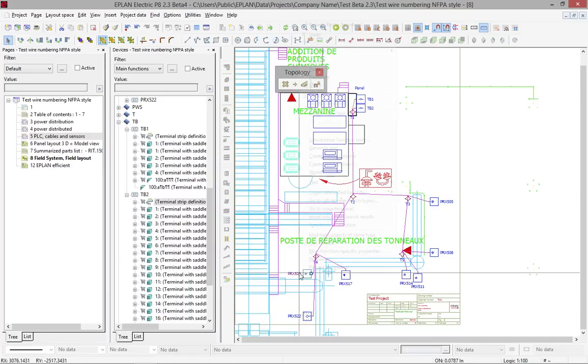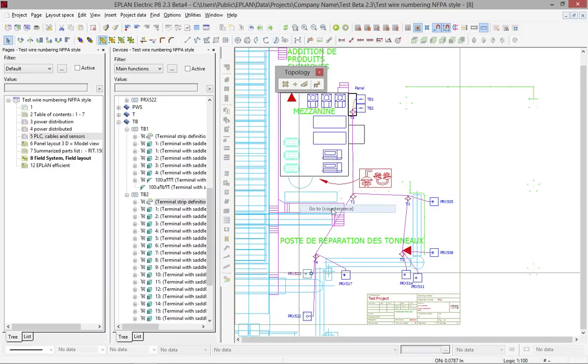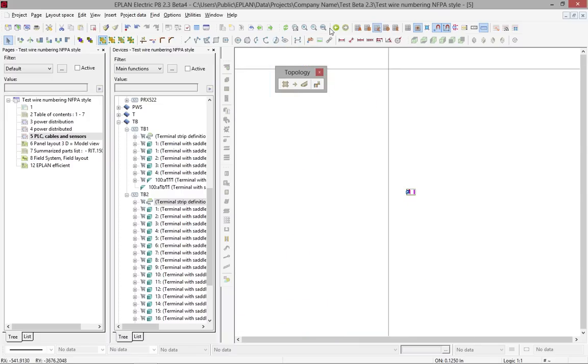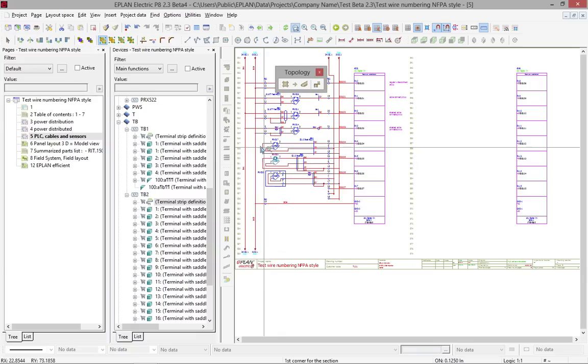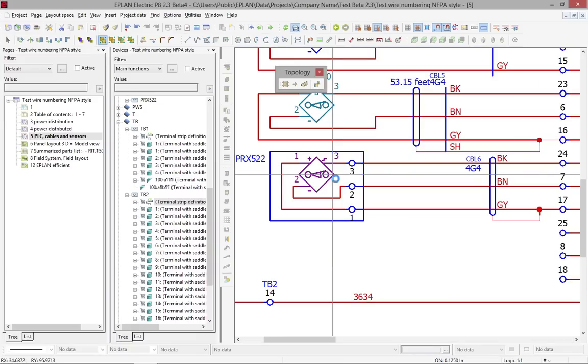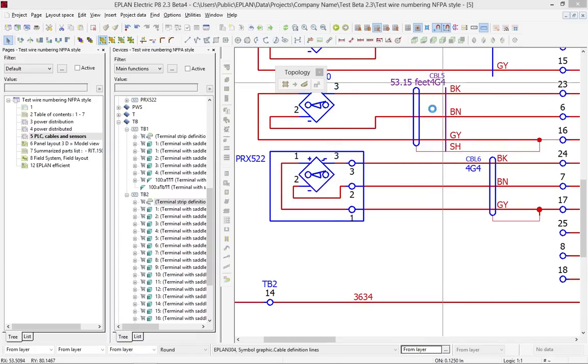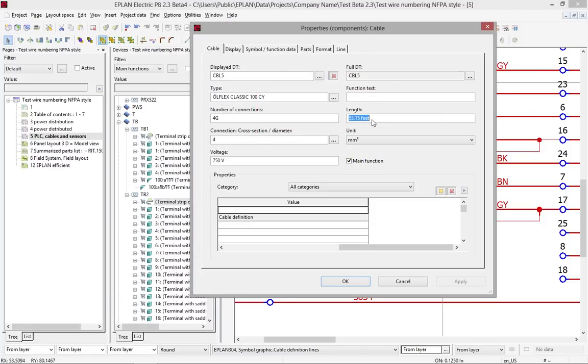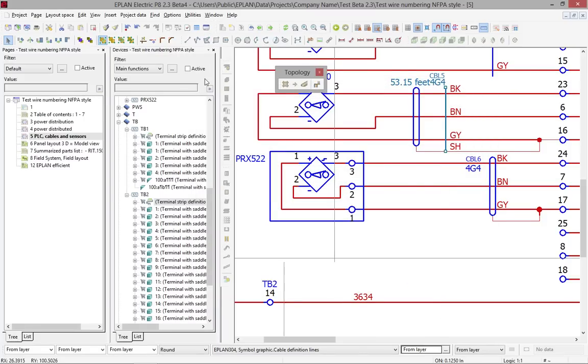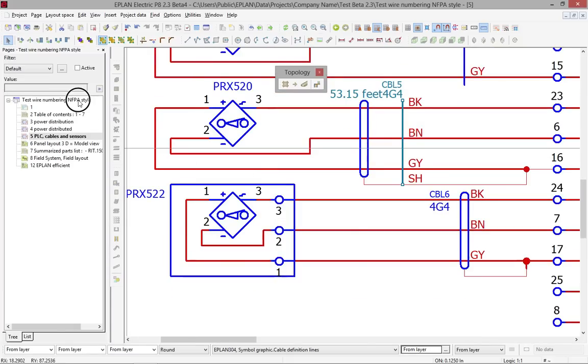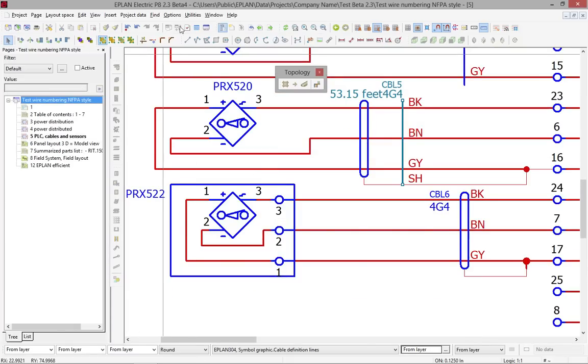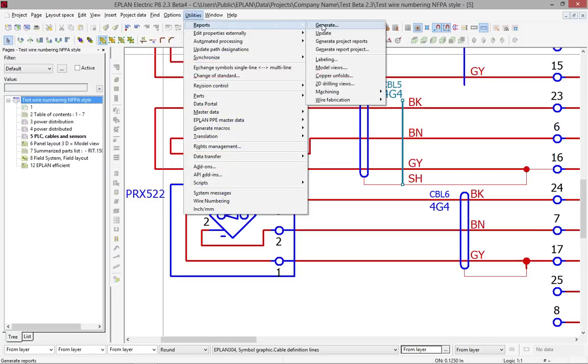Here I can use the right mouse click, go to counterpiece, to jump over to the other side. And of course here, you will see the cable that is assigned here automatically has a length assigned to it. This length that came here is actually the total of all the cable trays that are put together. The beauty about this is you don't have to calculate this. If you have to modify the topology, you can modify it, recalculate the length, and it will do it for you. This will reflect in all the reports.